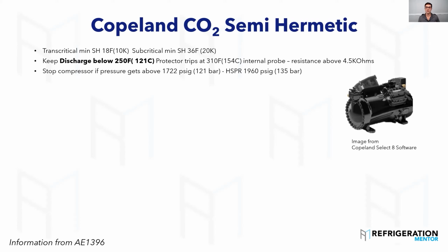This is an example: if your pressure gets above 1722, shut down that compressor. This is something you can program inside the controller, and on the ones that I've worked on, that's what they program a lot of. High pressure relief on the compressor, you can see it right over here, maybe.